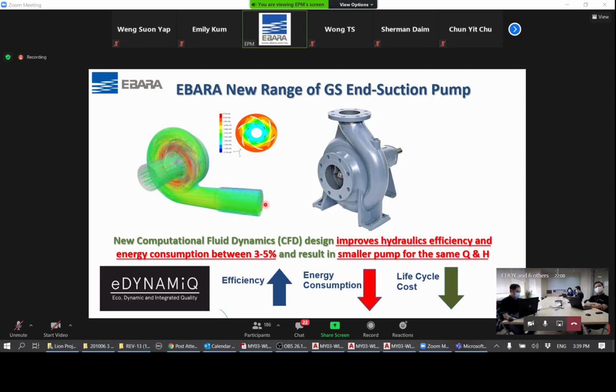But CFD is basically an engineering tool used to simulate the action of thermal fluids in a system. And it's used by many industries in their development work to analyze and to optimize and design things that actually have to either move liquids or cut through liquids or air. So CFD is a very important tool for this type of equipment. So this is where, by using advanced CFD methods, Ebara has improved a 100-year-old pump design to improve its hydraulic efficiency, and with that, it is able to improve the energy consumption easily by 3 to 5% from a normal pump that has an older design. And in some cases, it can even result in a smaller pump for the same Q and H, flow rate and the head.